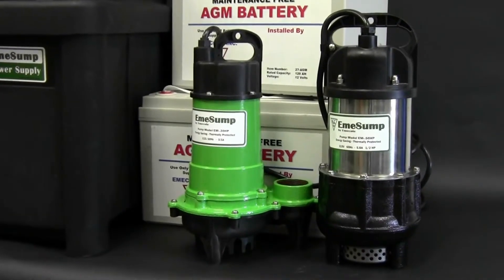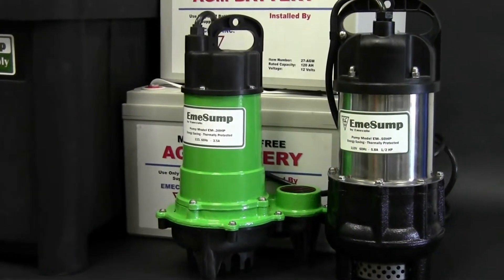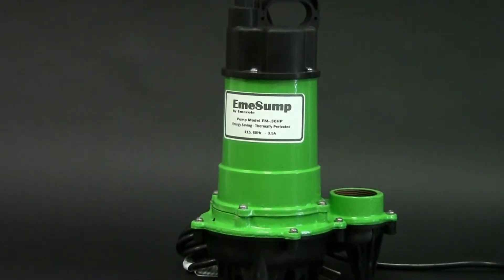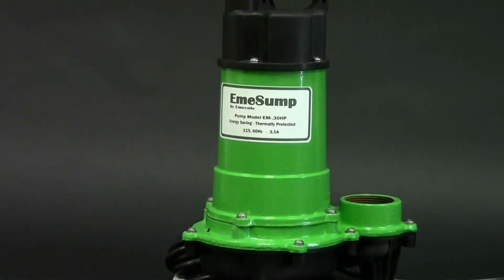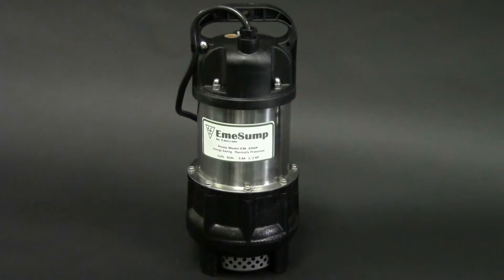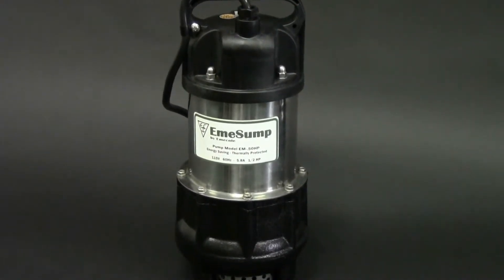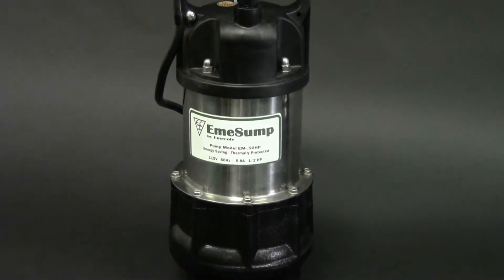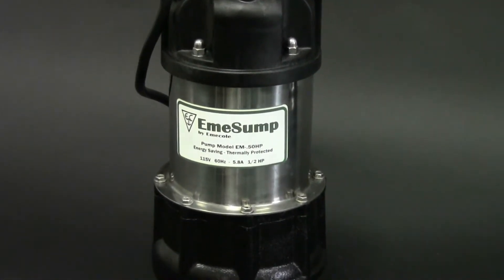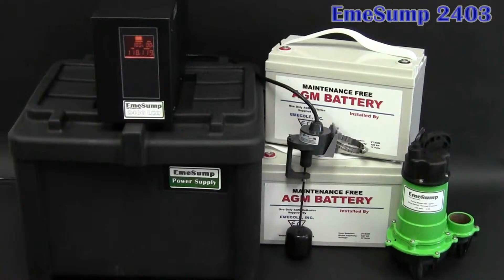The systems use high-capacity, efficient, and durable primary pumps as the backup pumps. The EmeSump in the 2403 system only uses 3.5 amps — about half the power that other 3/10 horsepower pumps use. The half-horsepower pump in the 2405 system only uses 5.8 amps, again about half the power of comparable pumps. The low amperage draw allows for less battery consumption and extended run times while maintaining a high pumping capacity.